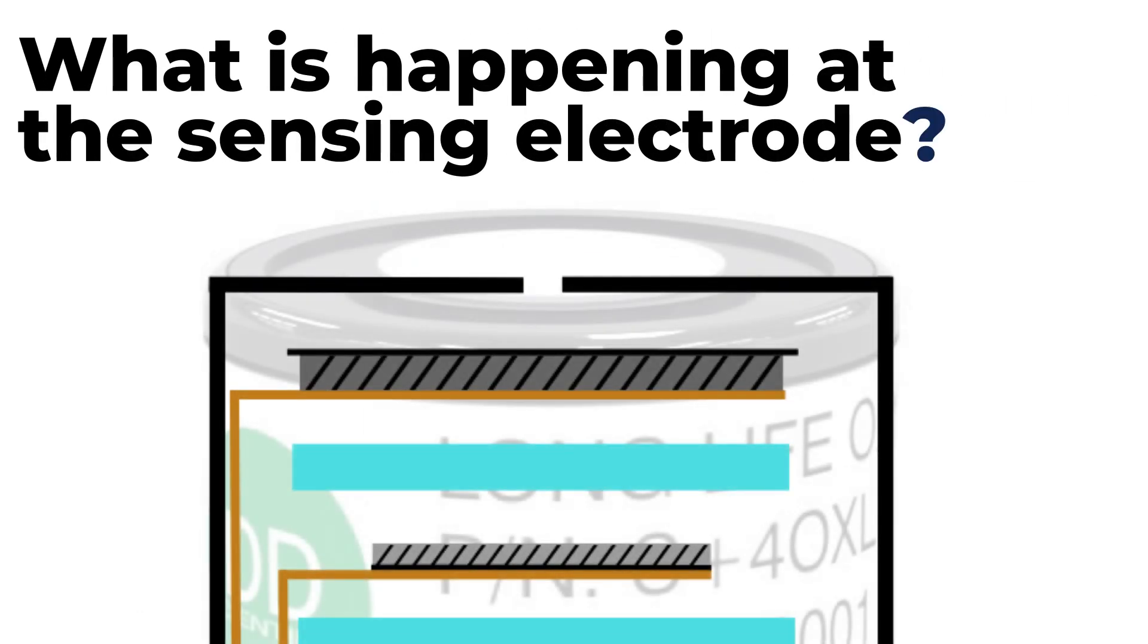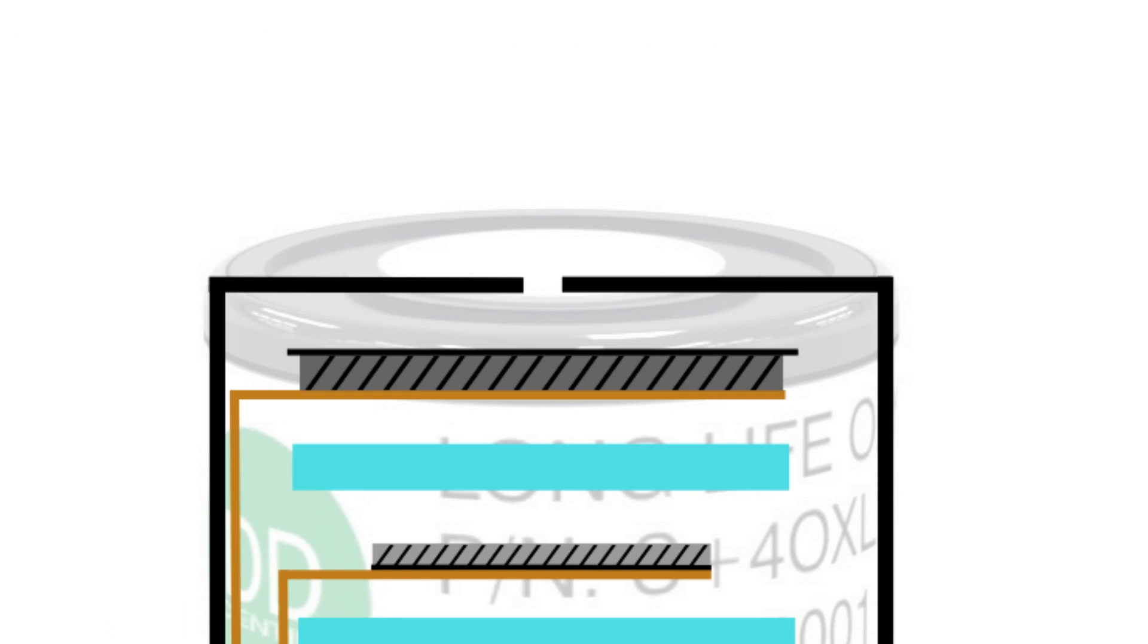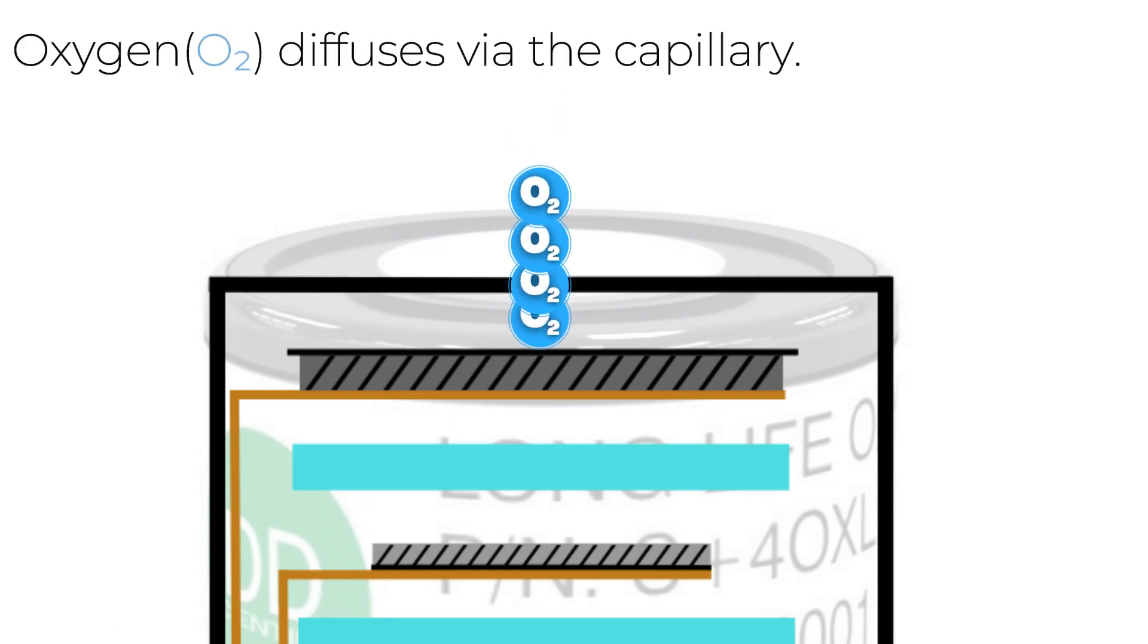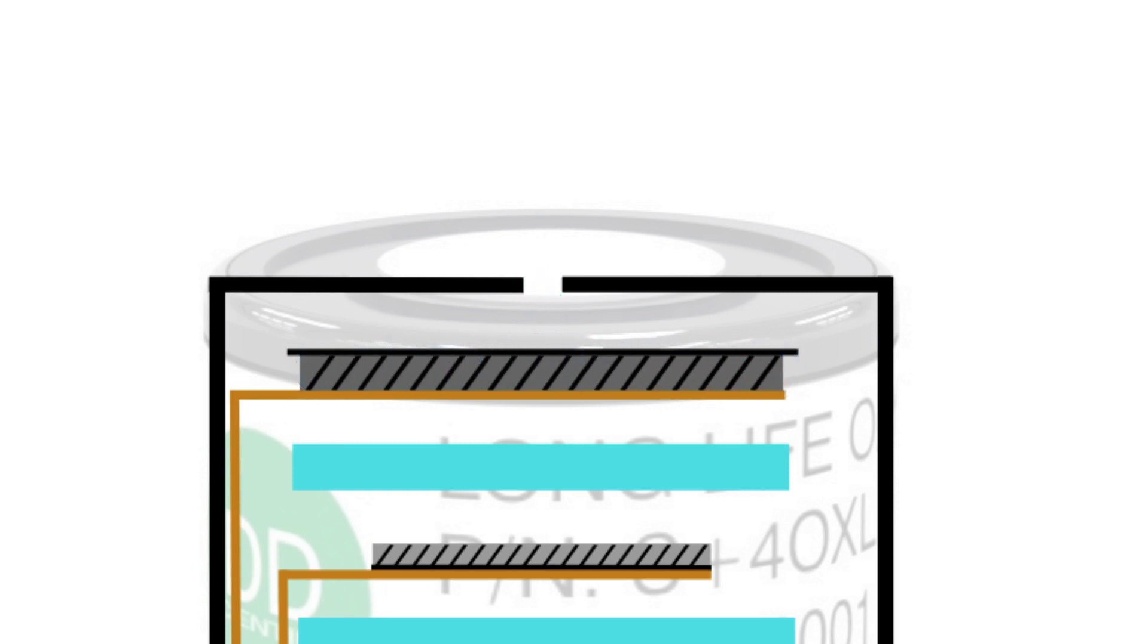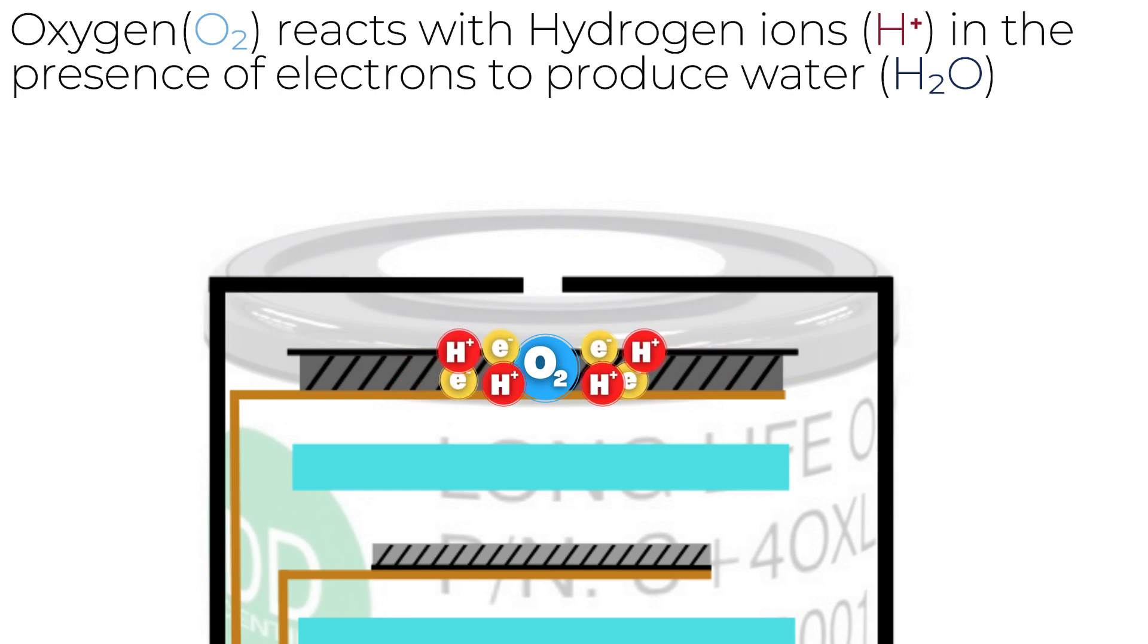So now let us talk about the chemical reactions which occur inside the sensor. As oxygen enters the sensor it encounters the sensing electrode where in the presence of hydrogen ions, also known as protons, and electrons it is reduced to produce liquid water.